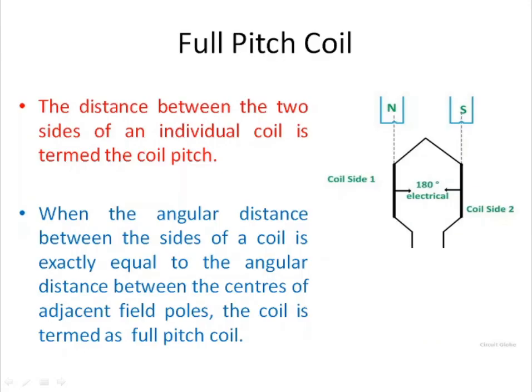Full pitch coil. The distance between two coil sides of an individual coil is termed as coil pitch. In a full pitch coil, the distance between two coil sides is 180 degrees electrical — that is, when the angular distance between the coil sides equals the angular distance between the centers of adjacent field poles. It is necessary to remember that the distance between two coil sides is 180 degrees electrical in the case of a full pitch coil.